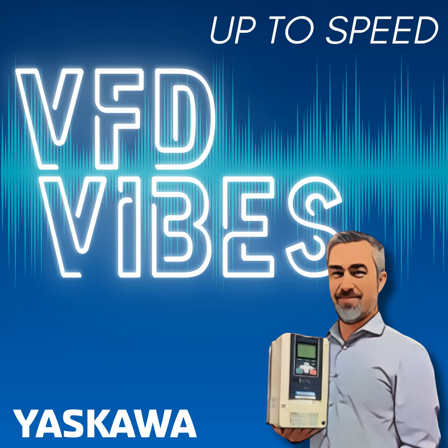There's so much you can do in real time just by having that data set into your controller. On the predictive and preventive maintenance side, you could look at things like DC bus voltage and monitor it, noticing trends starting to occur. Based on those trends, you can sort out that something might be wrong with the machine, maybe something is wearing down. You mentioned seizing up, maybe the current is starting to rise because a bearing is seizing up.